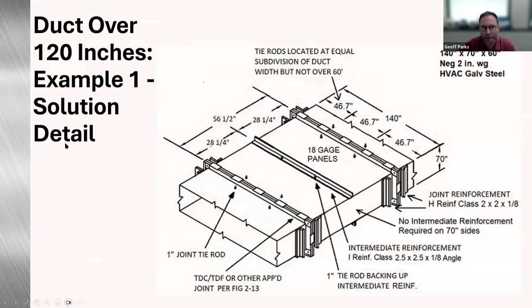So looking at this example, this detail shows you graphically everything that's required. So at our 70-inch side, we would have the 2 angles on either side. So that's reinforcing our 70-inch side joint. And then our 140-inch side, we have our two 1-inch EMT conduits. And then at our mid panel, we have our angle with our two 1-inch EMT conduits.